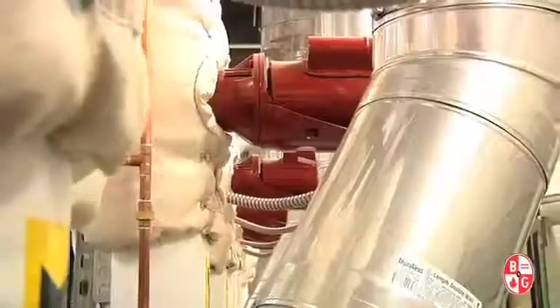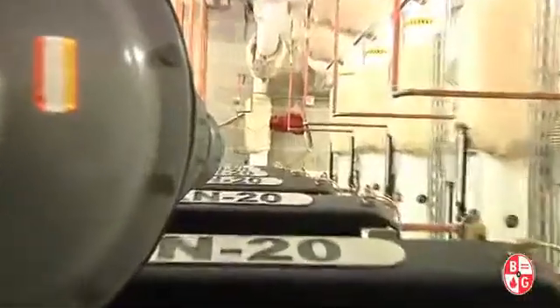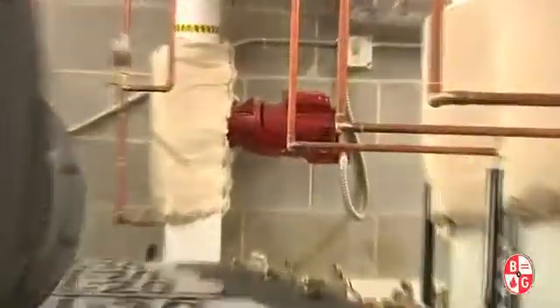The biggest problem was definitely the loop dynamics and the fact that you had 2 very different loops that were interconnected that operate in very different ways. In addition, we added several buildings that were on utility steam to the hot water loop, so that added additional complexity and pumping issues associated with that. All of the pumps associated with that heating plant are Bell & Gossett.